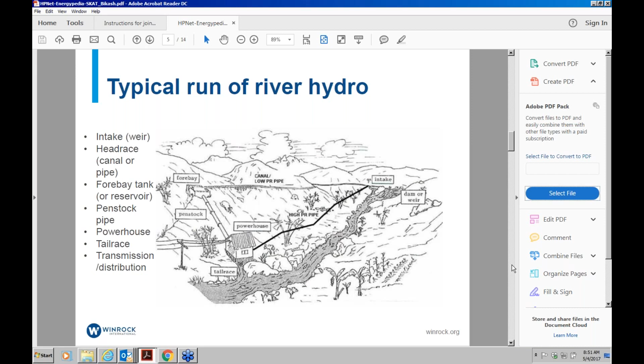So for a lower cost, you could get more power. The per-unit cost goes down if you can generate a high head with a short length of canal, which basically translates to the slope of the river. If the slope or gradient of the river is high—meaning it's a steep river—then for a short head race you can have a lot of head. That generally makes a good site, because you get more power for less water, or you can produce a lot of power, so both the per-kilowatt price and the per-kilowatt-hour price tend to be low. So that was the second point: river gradient or slope, the higher the better.